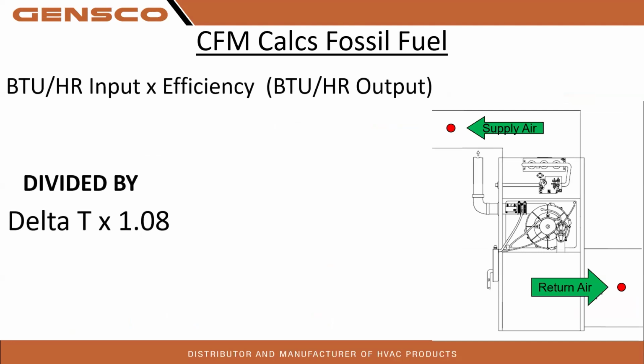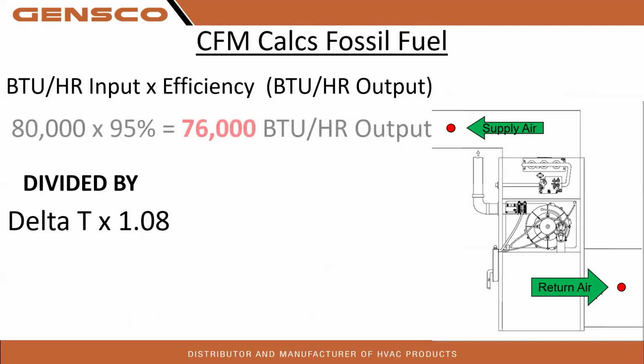Fossil fuel. So again, here's our BTU per hour input times efficiency. We'll go over that clock in the gas meter here in a second. 80,000 BTU input for the furnace. This is a 95% efficient furnace, which equals 76,000 BTU output. Our delta T is 65, which I do have a slide for an S9V2 where we get that correct temperature rise for the furnace.